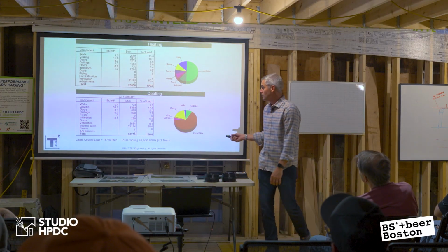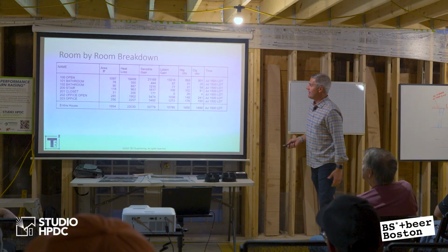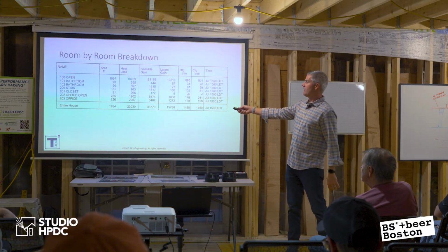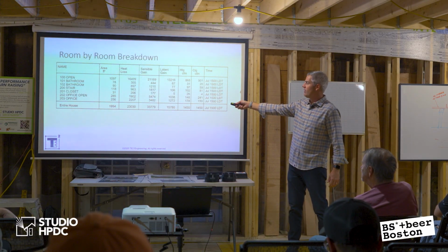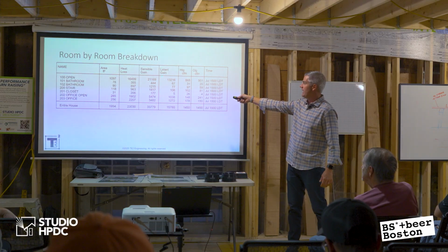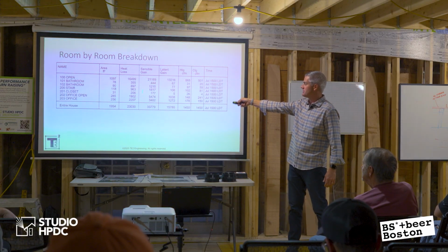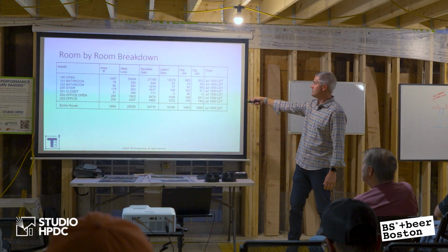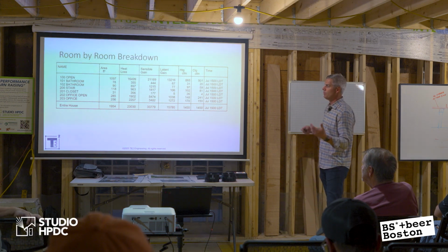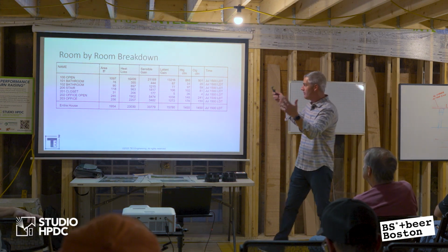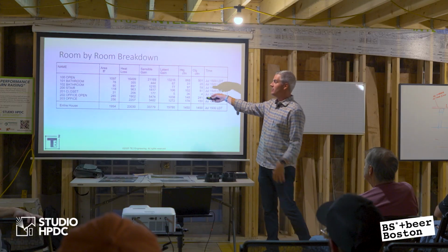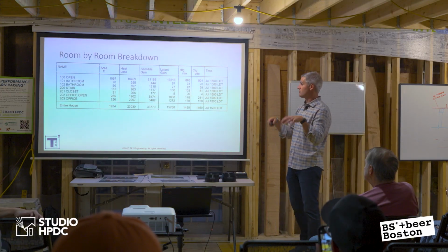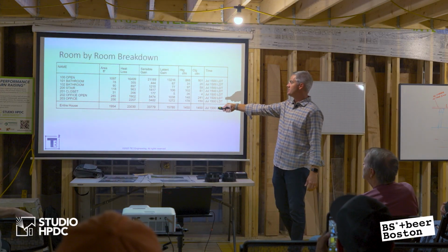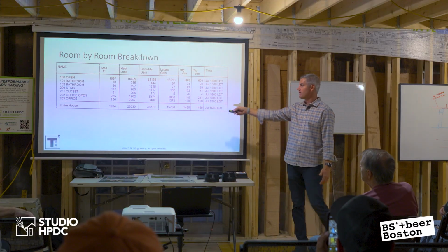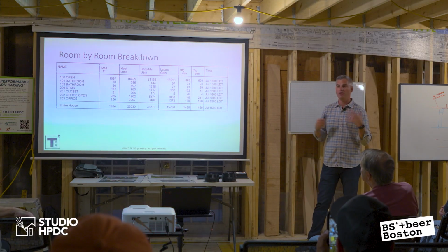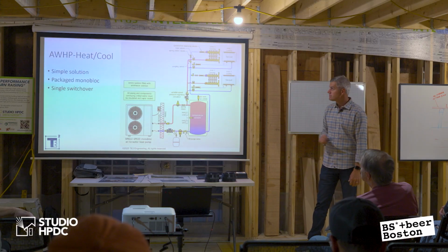Okay? So what's the room by room breakdown? Well, the open office area is about 1,000 square feet. You can see the heat loss and you can see the totals, sensible and latent, right here, 21 plus 13. So you can see the percentages of breakdown in terms of which rooms are the problem rooms. It's dominated by this open office space, what we're calling the conference room. And then upstairs, manageable loads, right? The office space upstairs, manageable. 3 people in there, not a big deal, right?